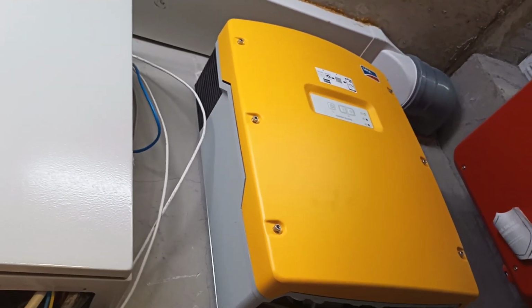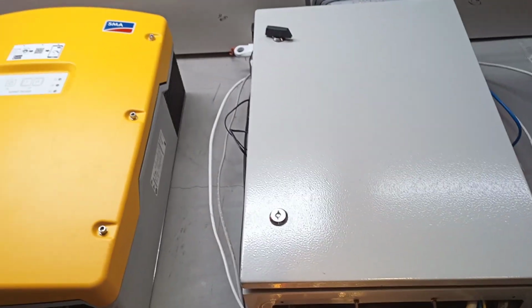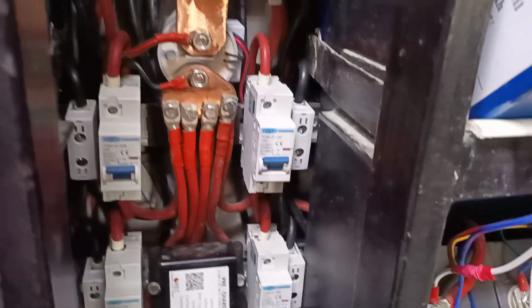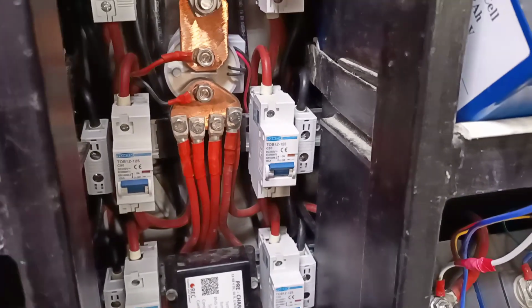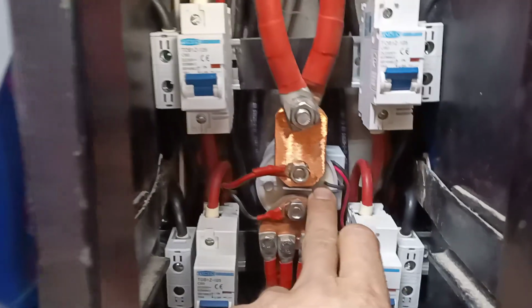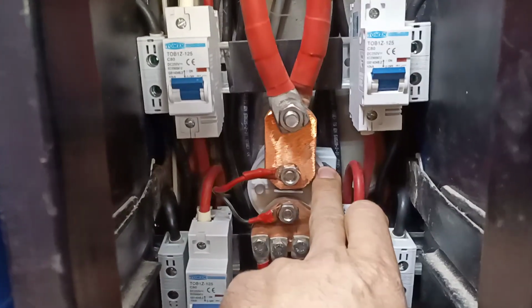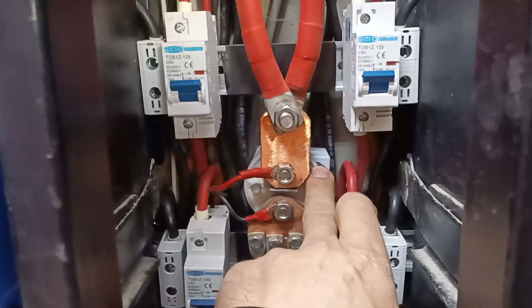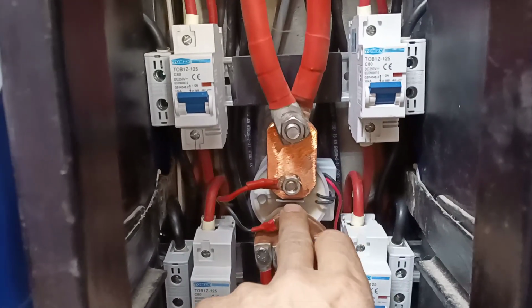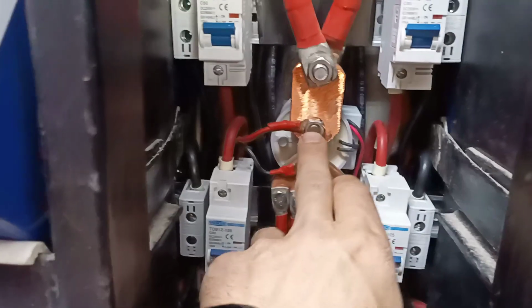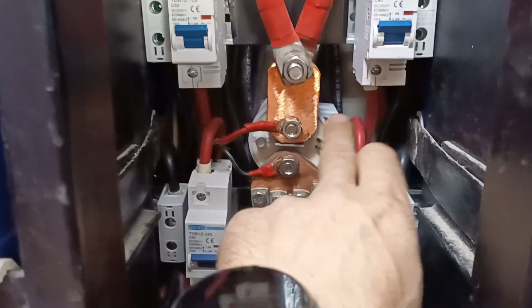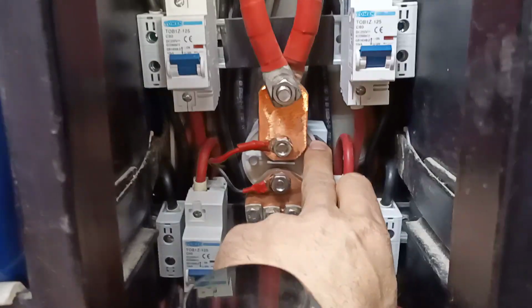These are 6 kilowatt Sunny Island inverters. They have very big capacitors inside, and 6 seconds is just not enough to pre-charge this inverter. Because of that, I ruined one of the contactors, because of the rush of energy - it welds the contactor inside.